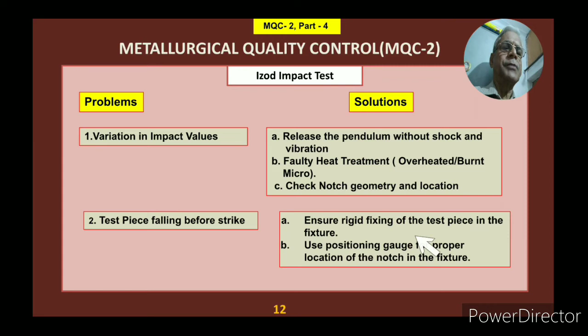Then test piece falling before strike. Sometimes you release the load and the test piece falls before striking. Then you have to repeat the test. Sometimes I have seen that when you release this, the piece breaks, but it is not in 2 parts. It remains in the fixture. If this is happening, then you have to again repeat the test. And for this, the solution is that you have to rigidly fix the test piece in the fixture. This is a must requirement. And use a positioning gauge for the proper location of the notch, so that the hammer strikes at the right position. So this positioning gauge has to be used for fixing the test piece in the fixture.